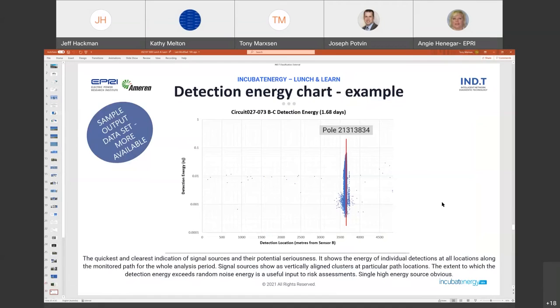Thanks, Jeff. This is one of the standard charts that early fault detection produces, part of the deep dive suite of charts available on the web portal. It shows the path that was on the last slide. Along the horizontal axis, you've got meters from sensor B. This is the chart of the path between sensors B and C. The vertical axis is the measured detection energy at all points along that path. The system uses a time of flight algorithm to locate things, and it measures the energy of the signal.